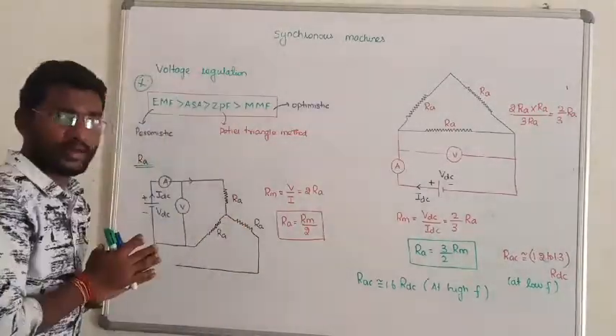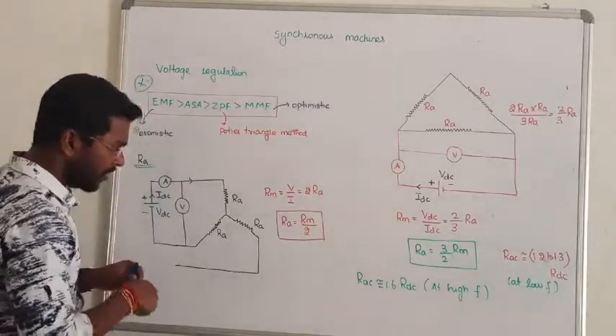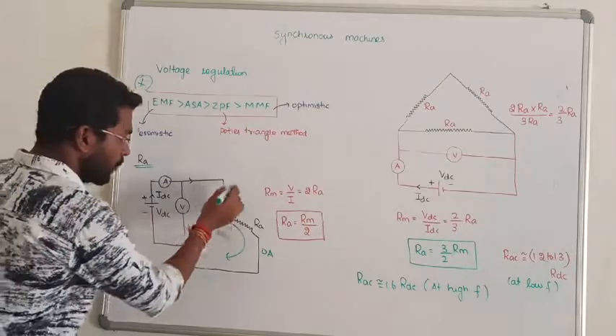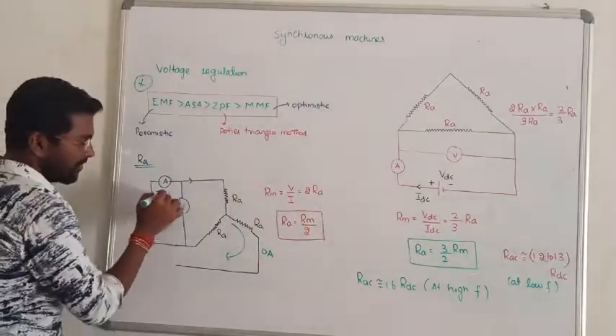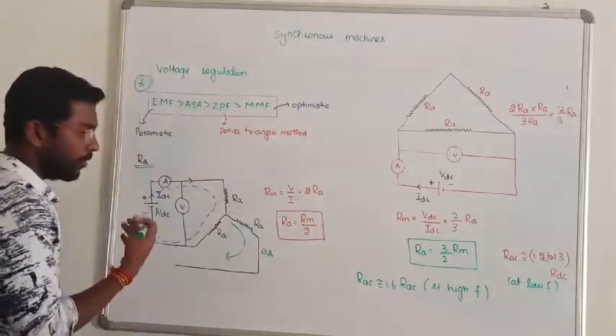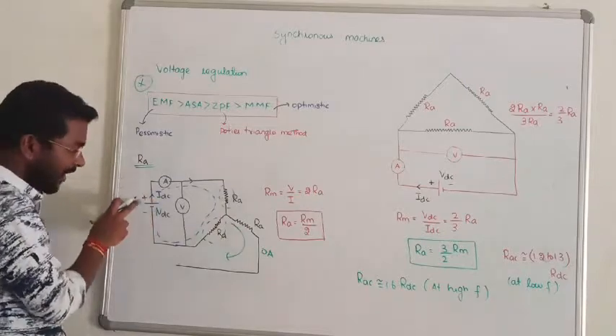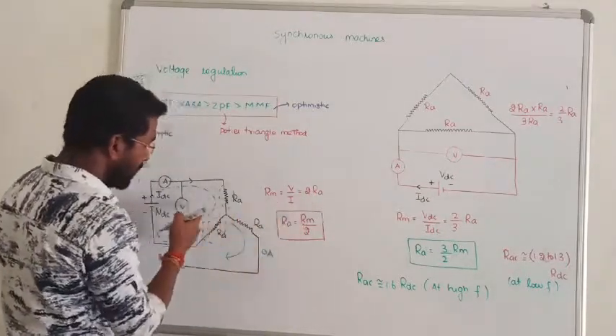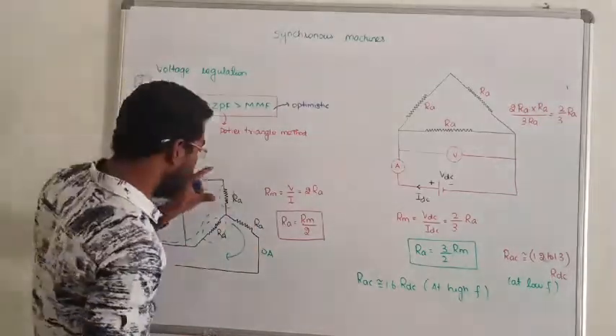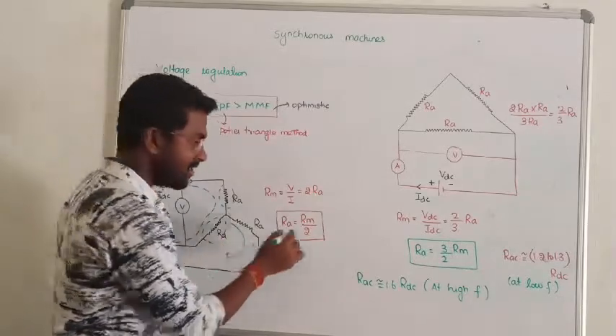If we connect with the star connection and supply DC, we will be able to measure the resistance. Because line to line, we have twice R_A. So if we connect across two terminals, the measured value will be 2 times the armature resistance.